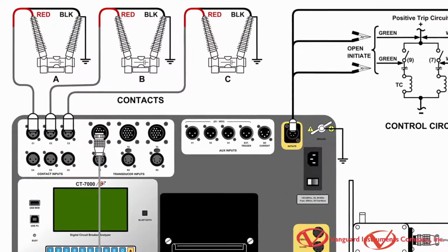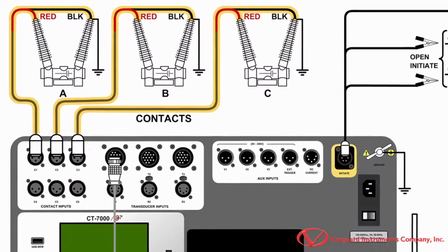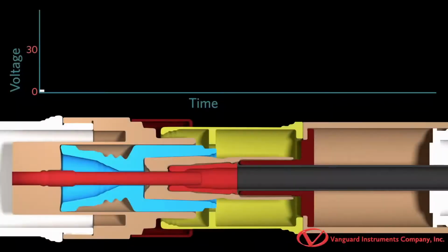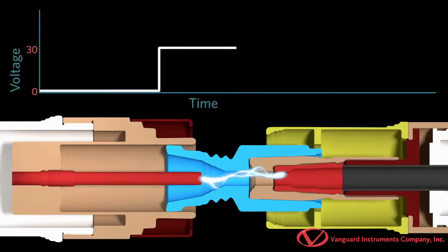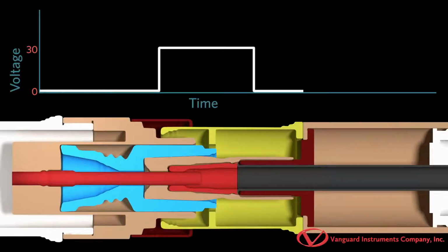Traditionally, when timing a circuit breaker, a DC voltage is applied across the breaker's contacts. The voltage drop across the circuit breaker's main contact is monitored during the opening and closing operations of the breaker. From this data, the opening and closing time of the main contacts can be determined accurately.